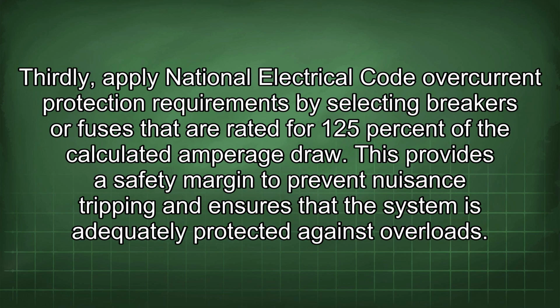Thirdly, apply National Electrical Code overcurrent protection requirements by selecting breakers or fuses that are rated for 125% of the calculated amperage draw. This provides a safety margin to prevent nuisance tripping and ensures that the system is adequately protected against overloads.